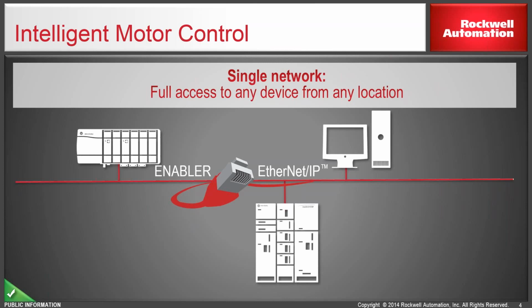So we're talking about having intelligence built into the motor control devices, be it fixed speed motors, variable speed drives, or motor control centers. Every device in the plant at the field level has its own intelligence built in via Ethernet, and that intelligence is given to the controller, and from the controller it goes directly to the enterprise level or to virtual devices like iPads or mobiles.